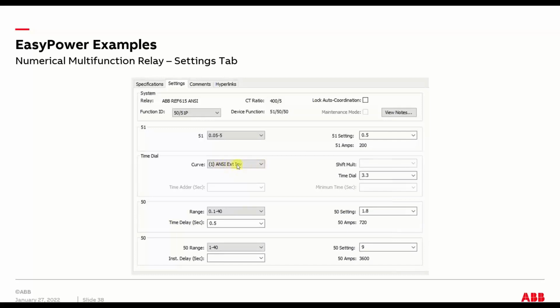Now, when you select this for this specific relay, you're going to get a whole list of curves. So I just selected the ANSI extremely inverse on this relay. Time dial setting, range. This is for your instantaneous protection. This 50 here is for your time delayed version of it, because you have a time delay plus a tap setting, and then this 50 here is for your instantaneous.